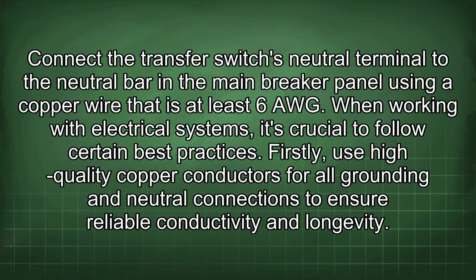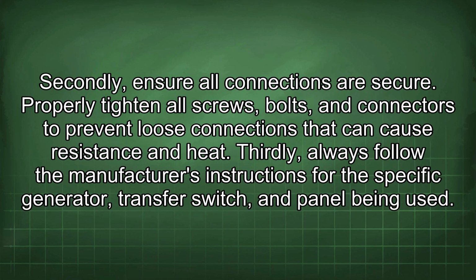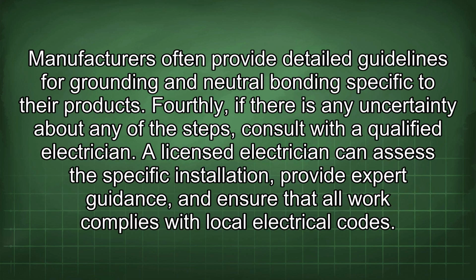When working with electrical systems, it's crucial to follow certain best practices. Firstly, use high-quality copper conductors for all grounding and neutral connections to ensure reliable conductivity and longevity. Secondly, ensure all connections are secure. Properly tighten all screws, bolts, and connectors to prevent loose connections that can cause resistance and heat. Thirdly, always follow the manufacturer's instructions for the specific generator, transfer switch, and panel being used. Manufacturers often provide detailed guidelines for grounding and neutral bonding specific to their products.